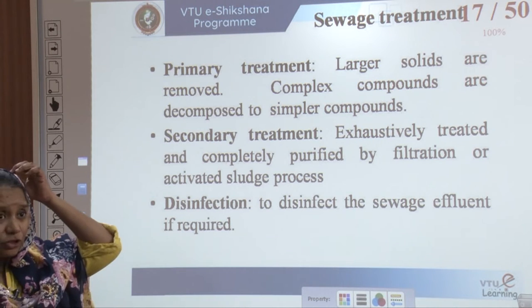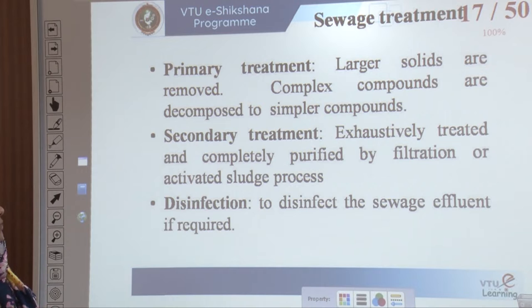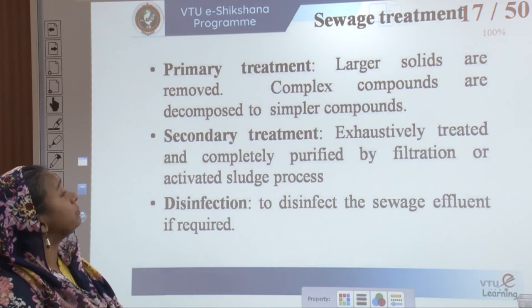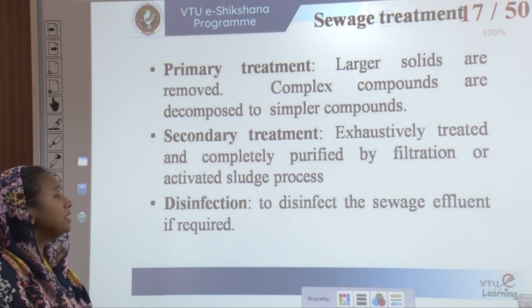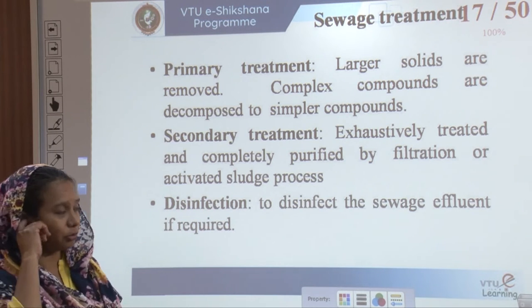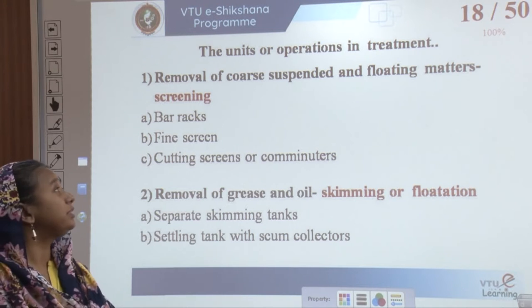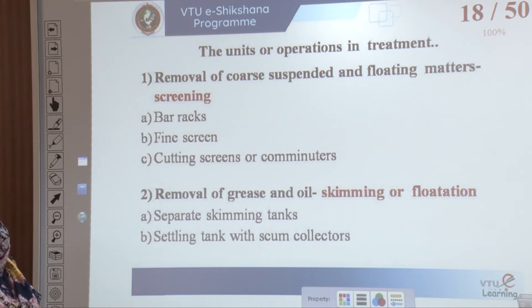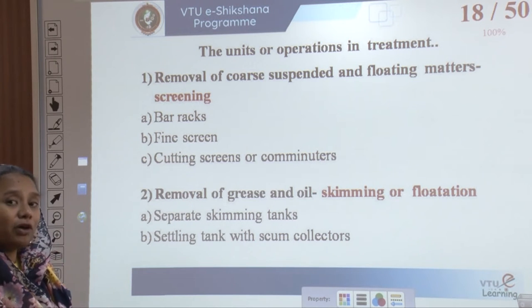Sewage treatment is divided into primary and secondary treatment. In primary treatment the larger solids are removed and complex compounds are decomposed to simpler compounds. In secondary treatment the sewage is exhaustively treated and completely purified by filtration or activated sludge processes. Third is disinfection, where the sewage effluent is disinfected if required. The units of operation for treatment are: first, removal of coarse suspended and floating matters through screening using bar racks, fine screens, cutting screens, or comminutors. Second, removal of grease and oil through flotation or skimming using skimming tanks and settling tanks. Third, removal of finely divided suspended matters through sedimentation and chemical precipitation.